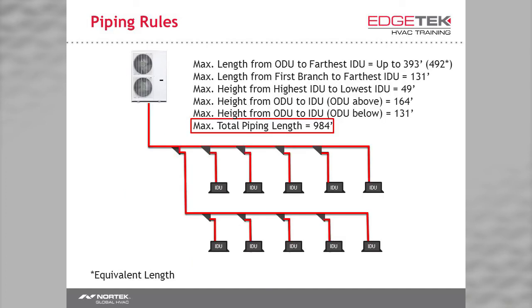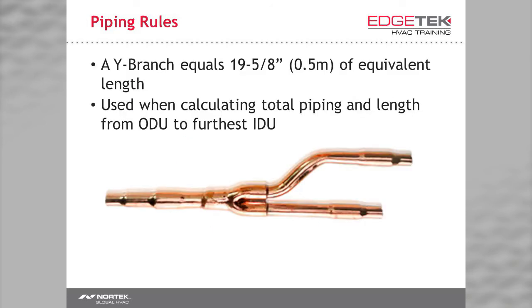If you add all the piping up in one direction, that total length cannot exceed 984 feet. That is a lot of piping, wouldn't you agree? For those equivalent length limitations, you have to factor in that Y branches are considered to be 19 5/8 inches long.